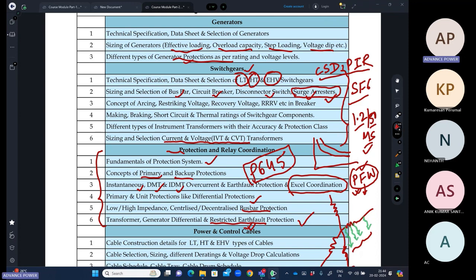Then for breakers, we'll discuss the concept of arcing. What is the re-striking voltage? How is the arc extinguished? What are the ionization and de-ionization phenomena? How does the dielectric strength of the medium change when you use different cooling mediums in the arc extinguishing chambers? Based on the recovery voltage and the rate of rise of recovery voltage, we'll discuss that in these chapters. We'll discuss components like making, breaking, short circuit, and thermal rating. So these four things are also very important.